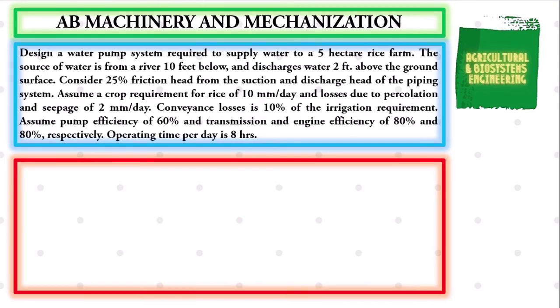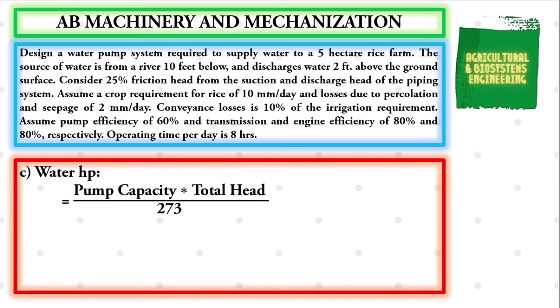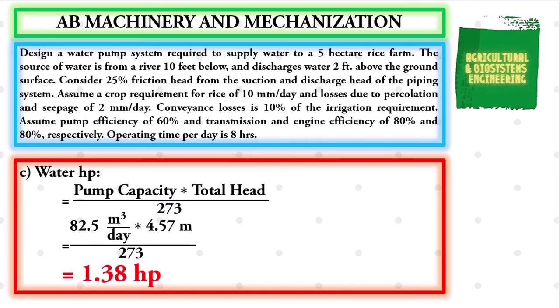The next value to solve is the water horsepower. Using the formula: Water HP = (pump capacity × total head) ÷ 273. Substituting: (82.5 m³/hr × 4.57 m) ÷ 273, giving us a final value for water horsepower of 1.38 horsepower.